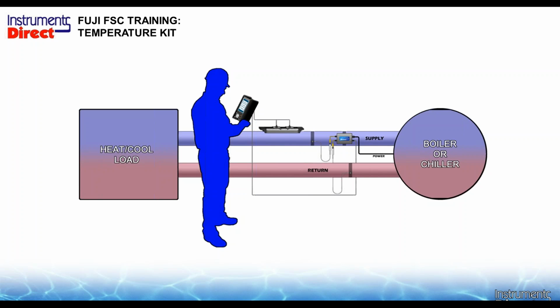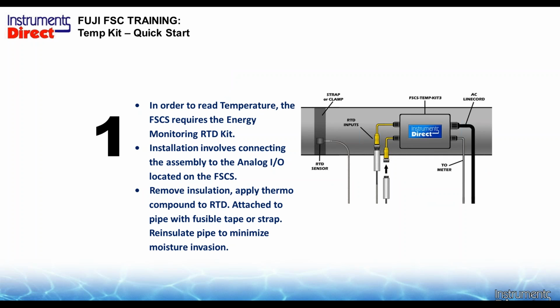For our advanced users who want to measure energy, measuring energy is an option that you can add to the Portaflow-C. It has clamp-on temperature sensors, and the way an energy application works on this heat and cold supply loop, there is basically a closed loop system. And so you will only need one flow meter, and most people tend to put it on the supply side. And what you're looking for in an energy monitoring is you need to measure flow, you need to measure temperature in the supply, and temperature on the return, and calculate the differential between these two, supply and return. So with all that data, we can come up with a BTU calculation, and of course it's stored on our data logger. So as we said, this is an option.